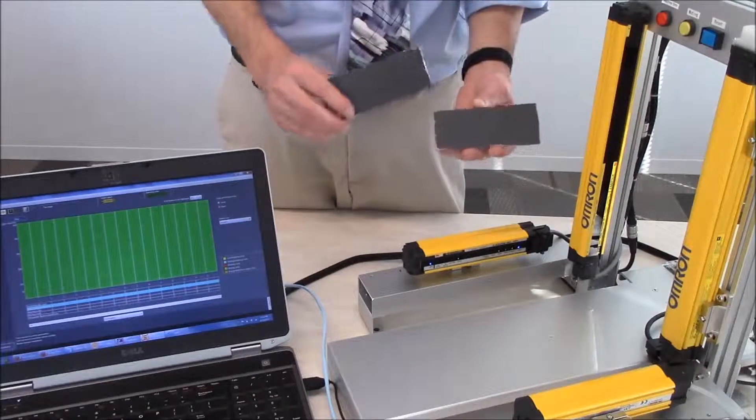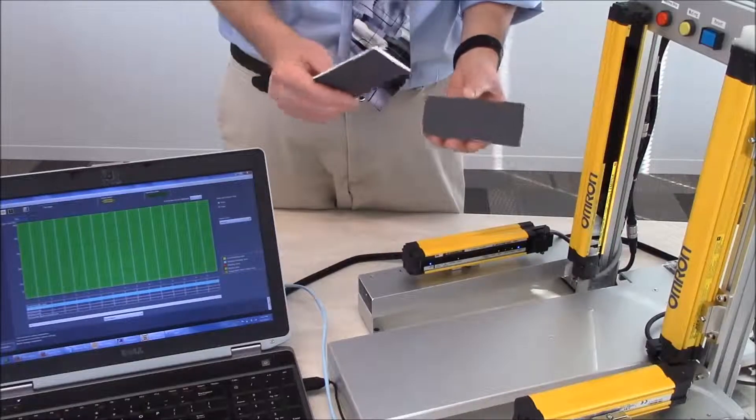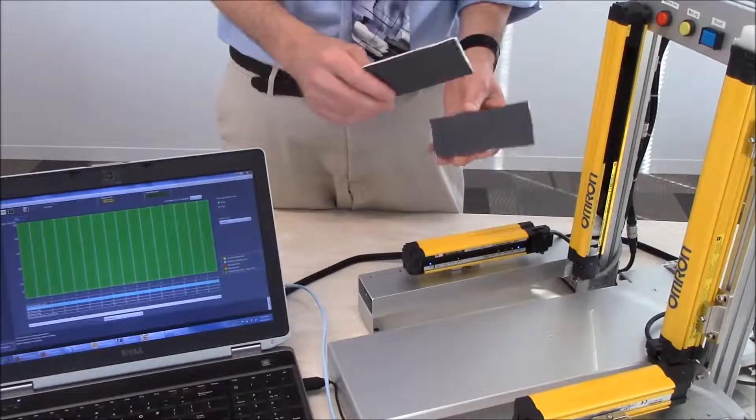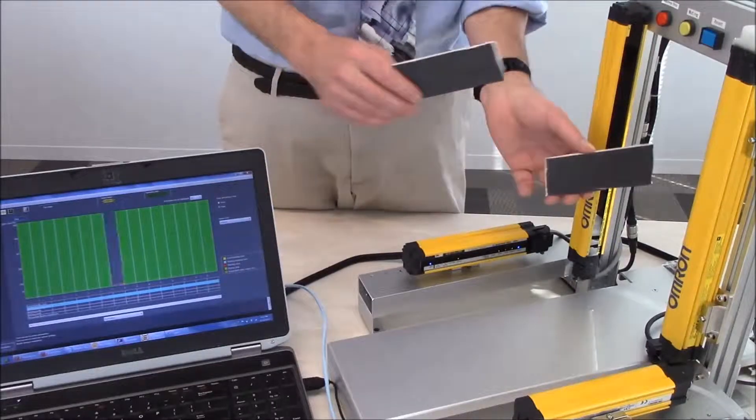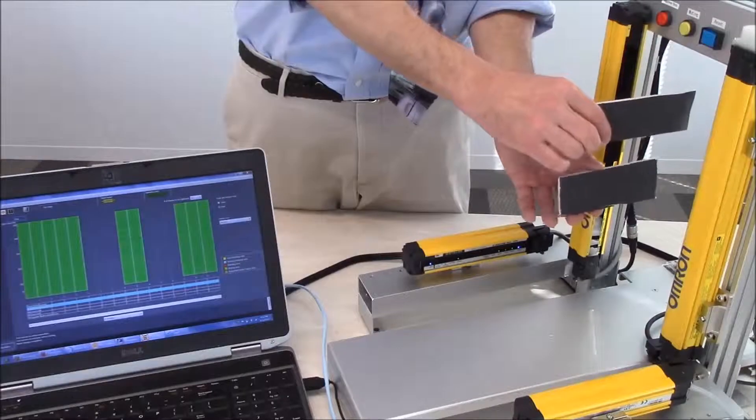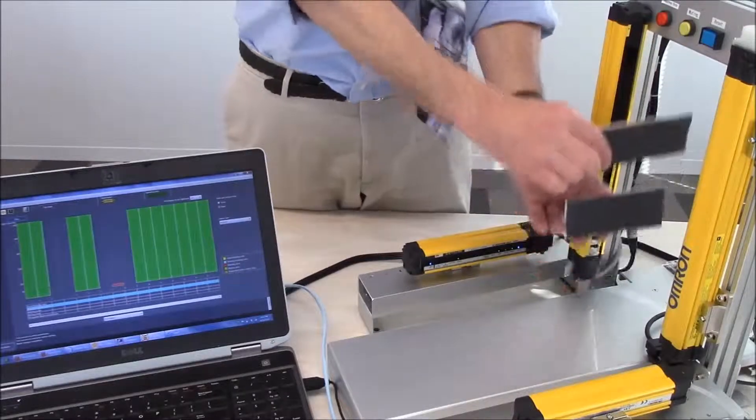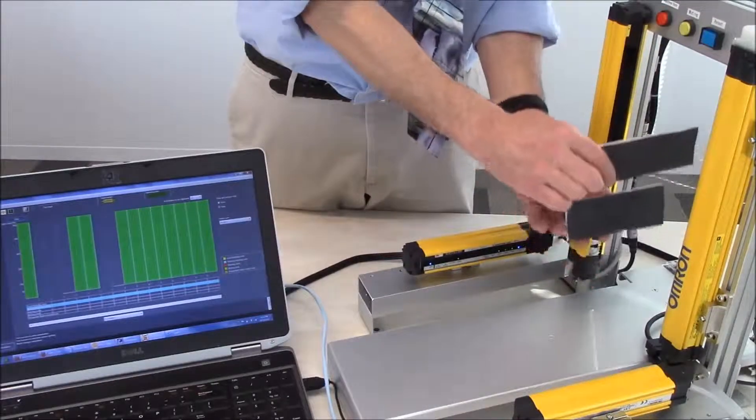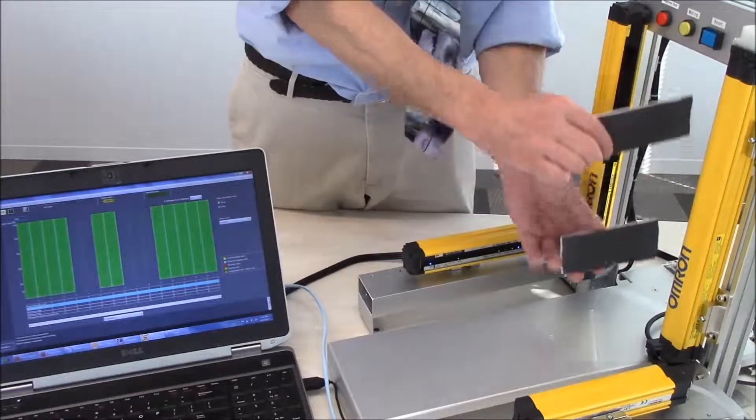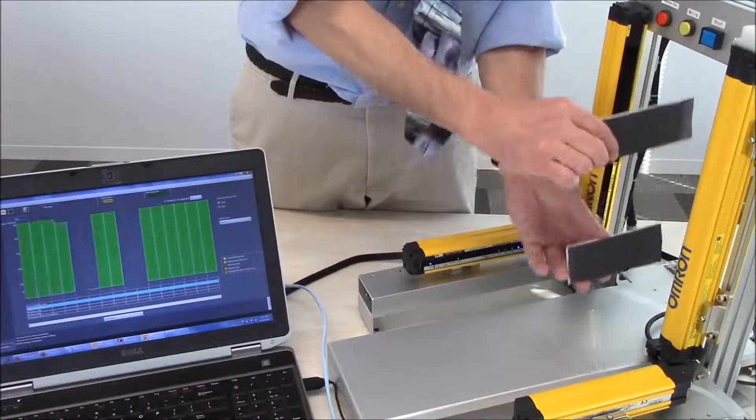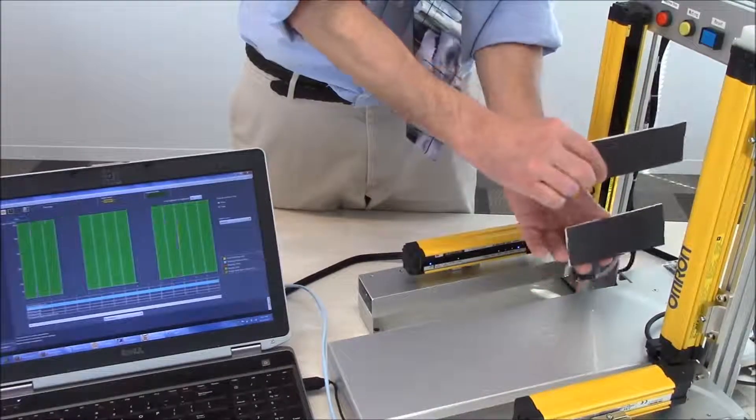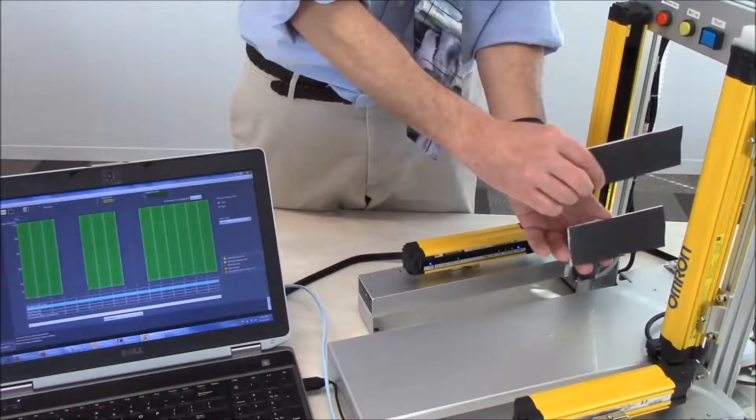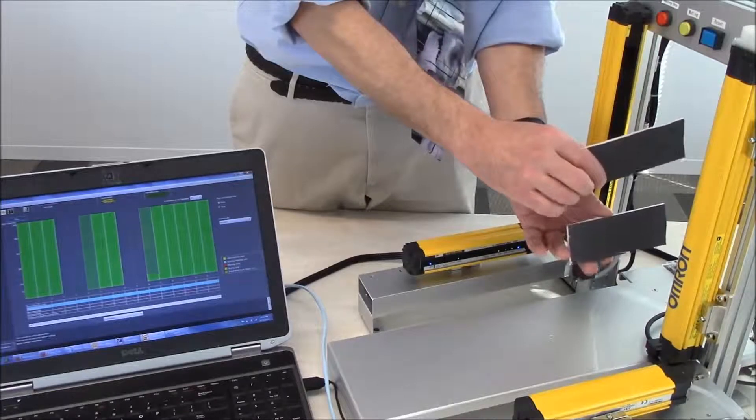Now presently I have a couple items here that are less than three beams in size. So I can throw them in the light curtain anywhere. I can move them up and down as you can see on the PC. I can move them apart. But as long as I don't break more than three beams, I am okay.